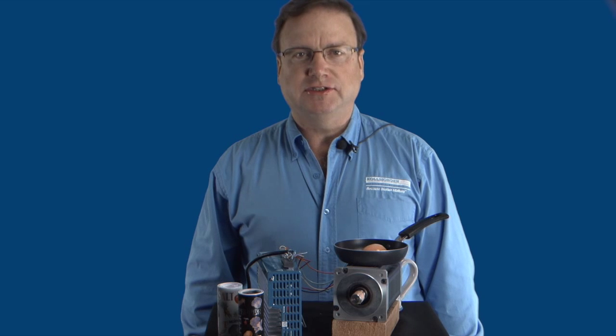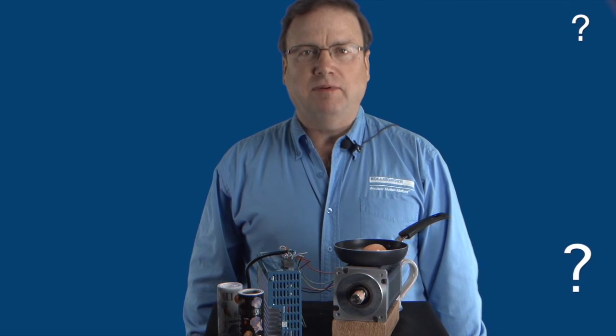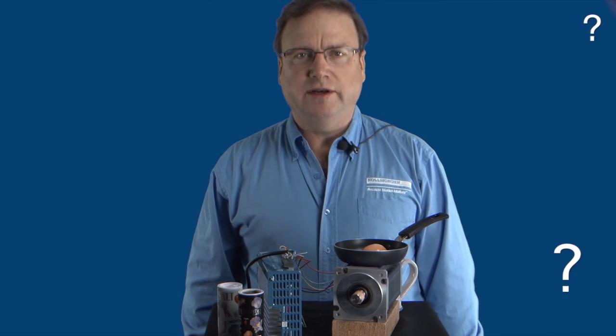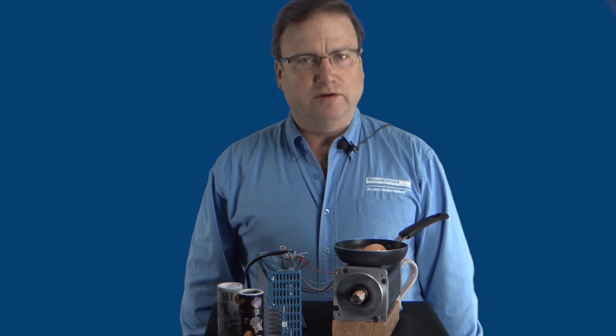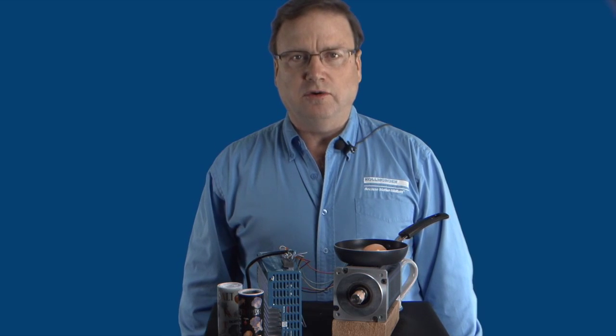One interesting thing about a step motor is how you drive it. Most of the time operating a step motor, you are applying peak current through the windings, not just when you run, but also when you stop and are sitting at idle. The longer the on time, the more the motor will approach its rated ultimate temperature.